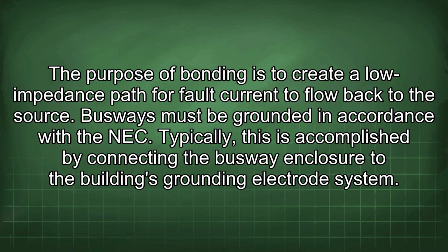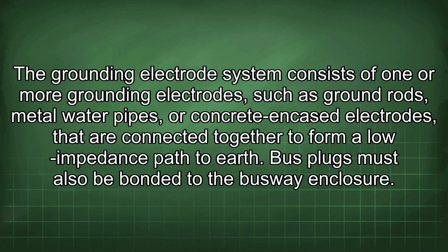Typically, this is accomplished by connecting the busway enclosure to the building's grounding electrode system. The grounding electrode system consists of one or more grounding electrodes, such as ground rods, metal water pipes, or concrete encased electrodes that are connected together to form a low impedance path to earth. Bus plugs must also be bonded to the busway enclosure.